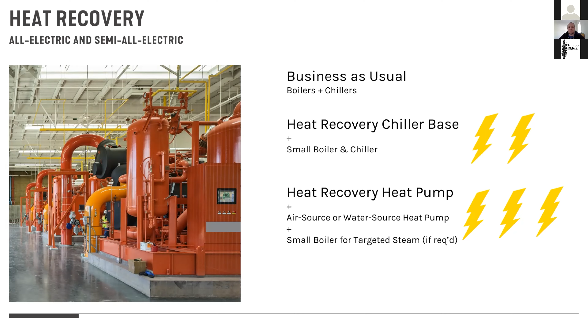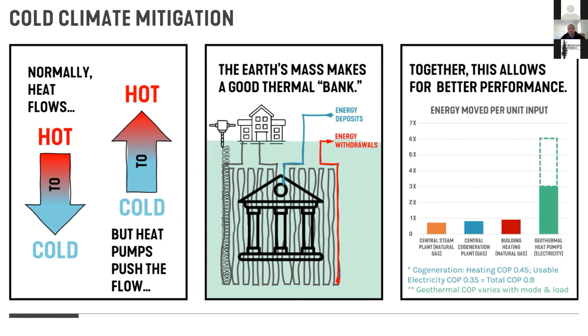So one of the big things that we do in cold climates, as I mentioned, is look for other places to store or pull heat out of. And a really great one from a market standpoint in the Midwest, upper Midwest, is geothermal or geo-exchange. That is because drilling costs there are very low compared to out here. And we can just beat the pants off of the COP, or coefficient of performance, when we do that, based on any fossil gas system.